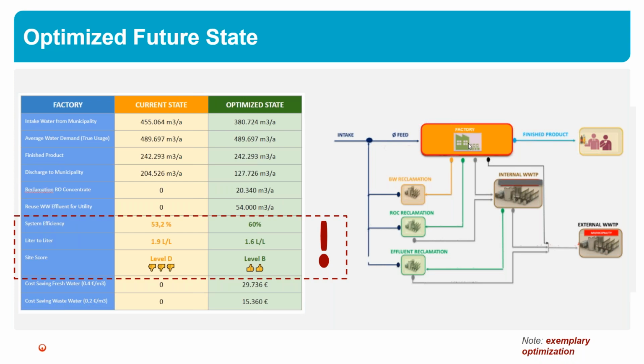As you can see here, this factory has its own wastewater treatment plant, and the effluent is normally discharged to the external wastewater treatment plant. But what we can do is take the treated effluent and put it through a second effluent reclamation, and this water can be used for non-production purposes. In this case it can be used for the cooling tower, because cooling towers have a huge water demand. With these improvements, which we suggested after the audit, the system efficiency can be increased to 60%, with cost savings of around 45,000 euros.